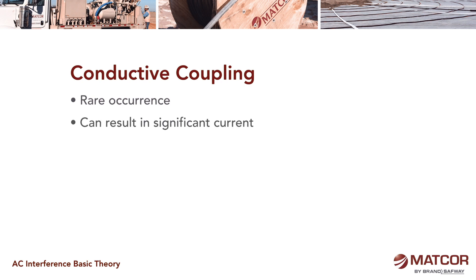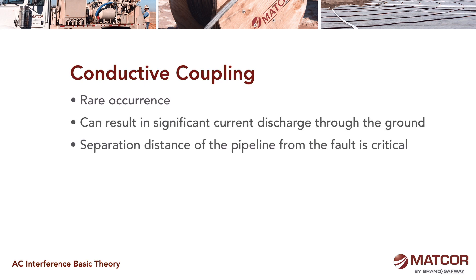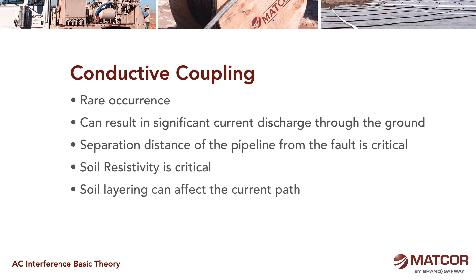Conductive couplings are rare occurrences but can result in significant current discharging through the ground. Separation distance of the pipeline from the fault is critical, and soil resistivity is critical. There can be soil layering effects — you could have a dry layer and a wet layer — and the arc would go through the wet layer. So we often have to measure soil resistivity at different layers or depths to make sure we have a good profile of where arcing can occur.